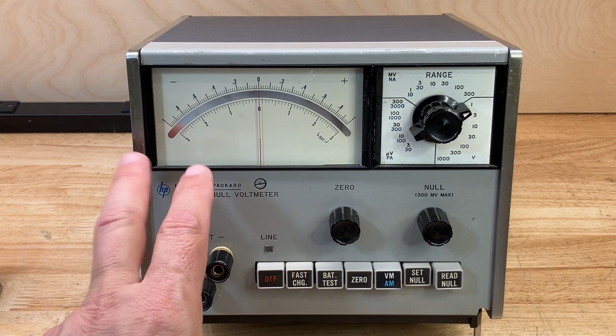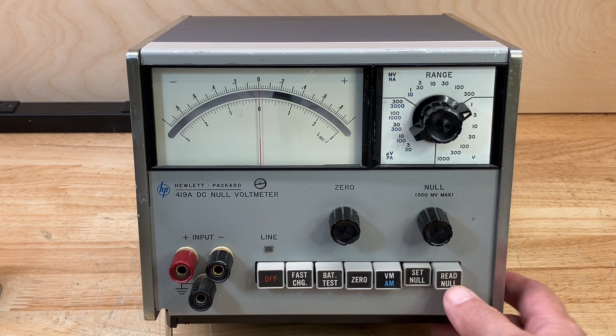So it's very important to not draw any current from a Weston standard cell. So that's what this voltmeter was used primarily for. Once you've set that null voltage to exactly counteract the input voltage that you're measuring, you select the read null function on the front panel, and it will read the battery voltage that you just dialed up with the null potentiometer. And what that means is you will only draw current from the internal battery when you're making a measurement. You will never draw current from the input terminals. The input terminal will always remain as infinite input impedance when you have properly nulled this instrument.